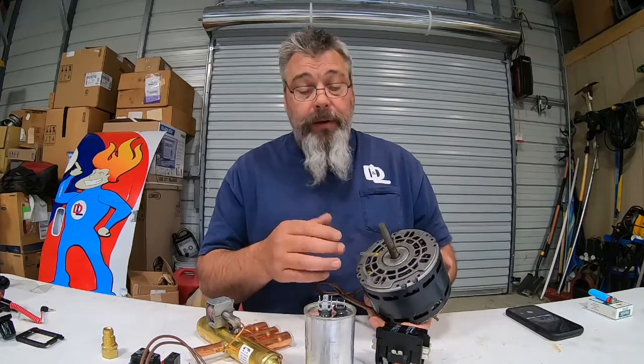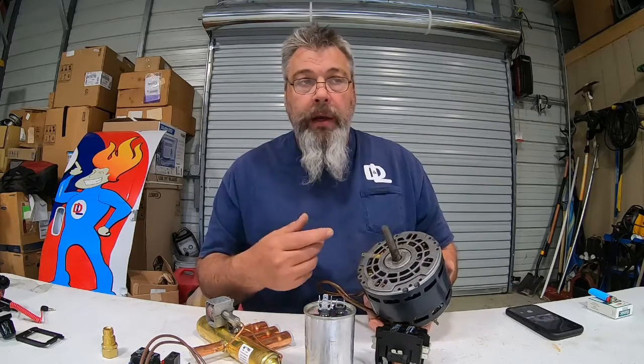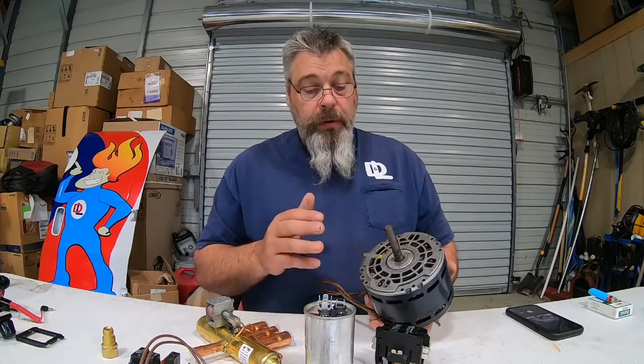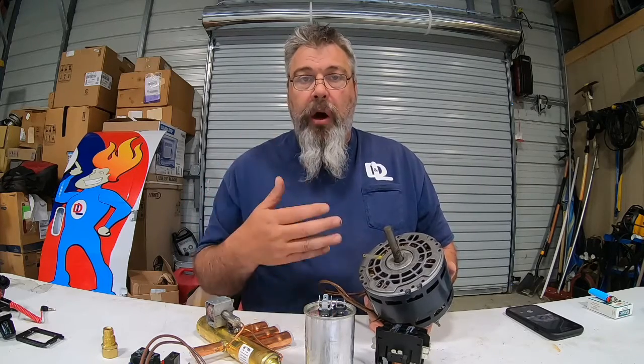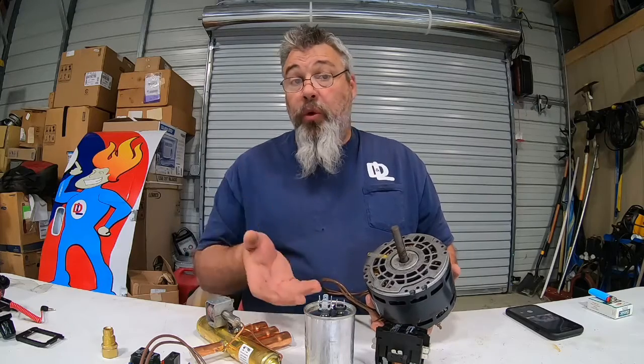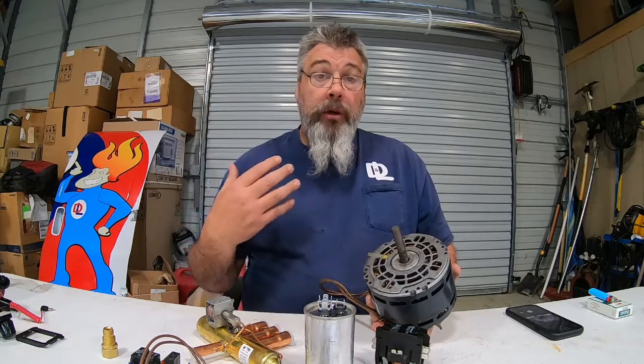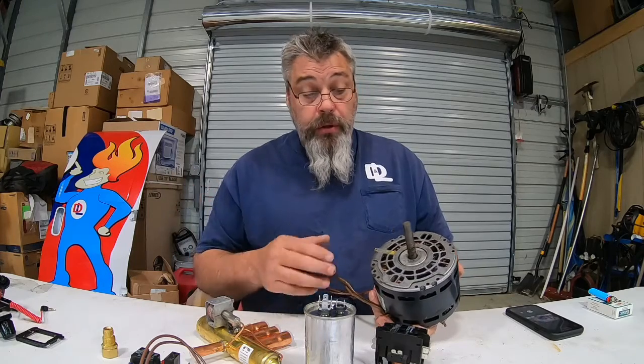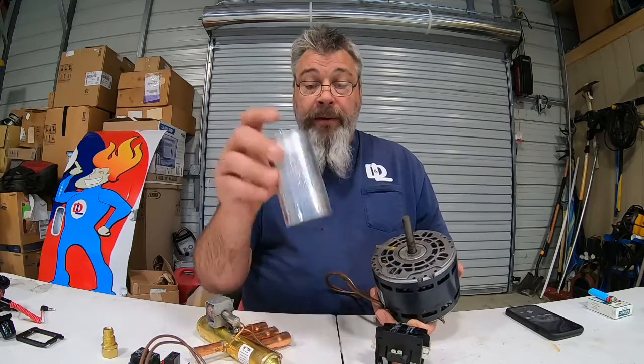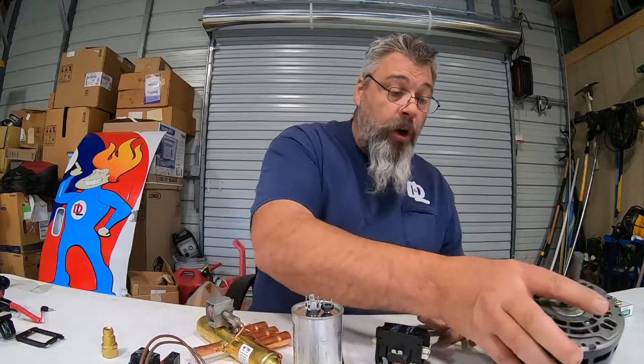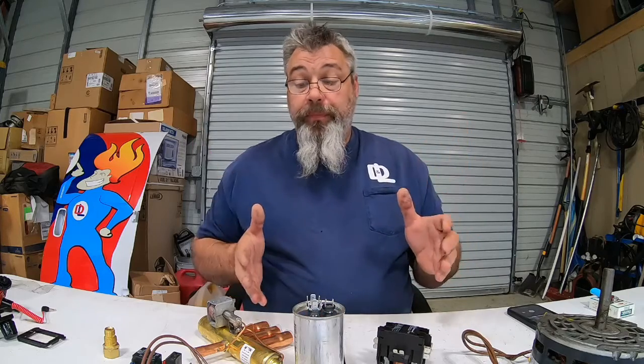Condensing fan motors do go bad. The bearings go inside. They start to whine, or they'll just quit forever. Sometimes they'll start to slow down. As they heat up, they slow down. That could raise your head pressure on your heat pump or your AC unit and cause some problems. Condensing fan motors are pretty common, along with capacitors, to go bad. And the last thing I want to talk about, which I don't have one here, which I wish I did, is a compressor. The compressor is the main heart of your system. And what that does is it compresses. It's exactly what it says it does. It compresses.